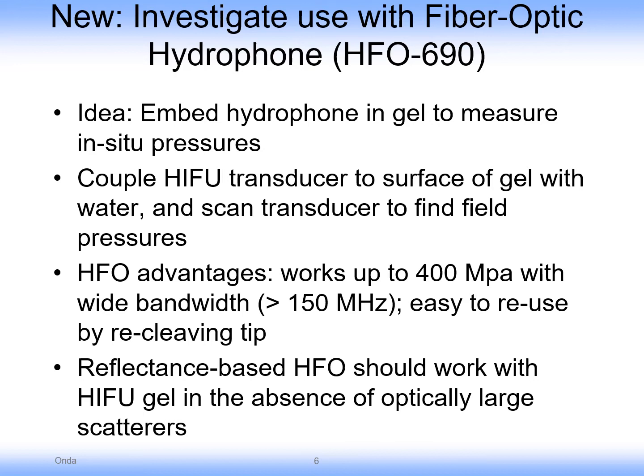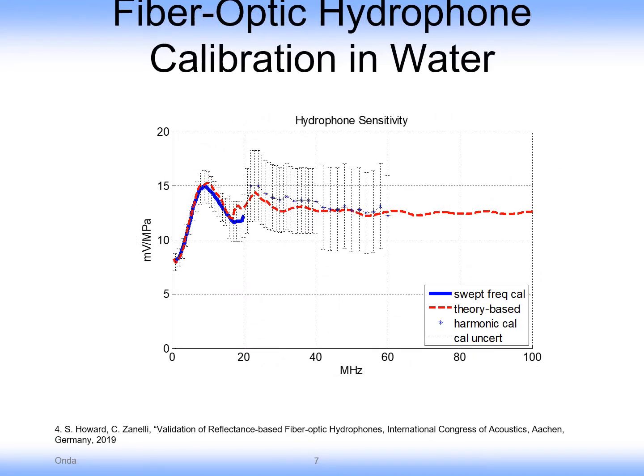The present work discusses the use of another product of ours, a fiber optic hydrophone, embedded in the HIFU phantom. The fiber optic hydrophone is very well suited for measuring HIFU because of its wide bandwidth and ability to withstand high pressures up to hundreds of megapascals. The use with this particular phantom is very attractive because of the optical clarity of the phantom and the lack of large scatterers which would interfere with the operation of the hydrophone. This is an example of the calibration which was done in water for the phantom.